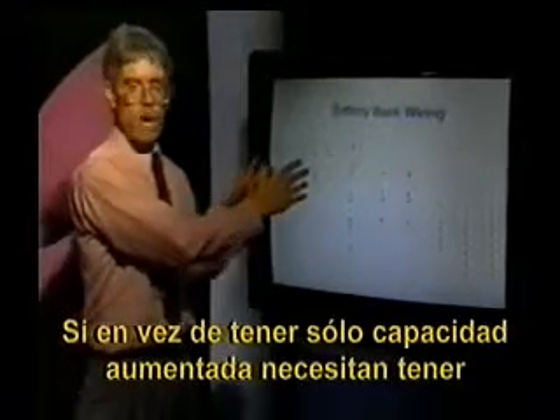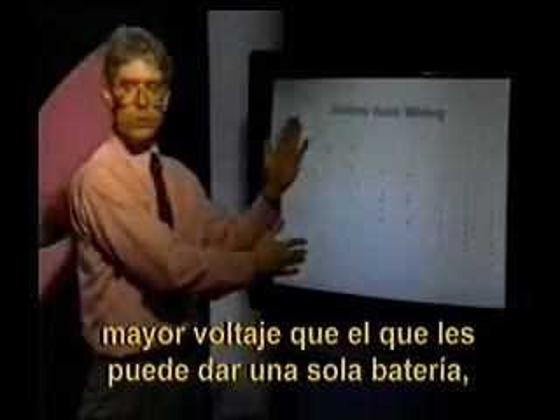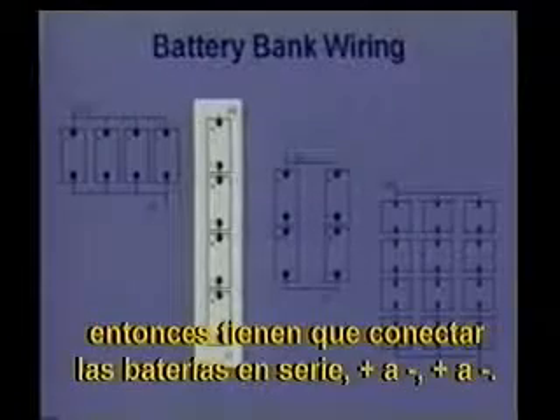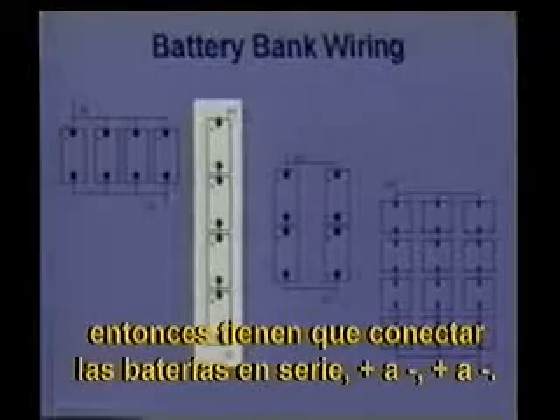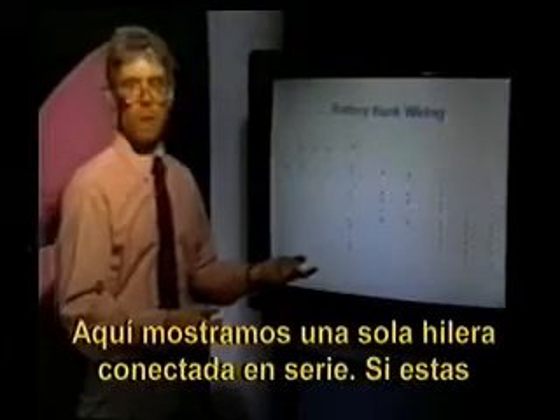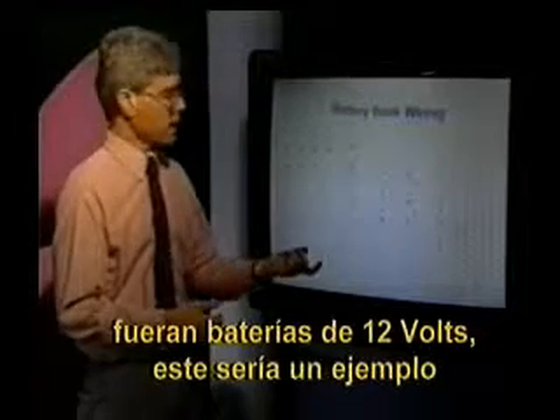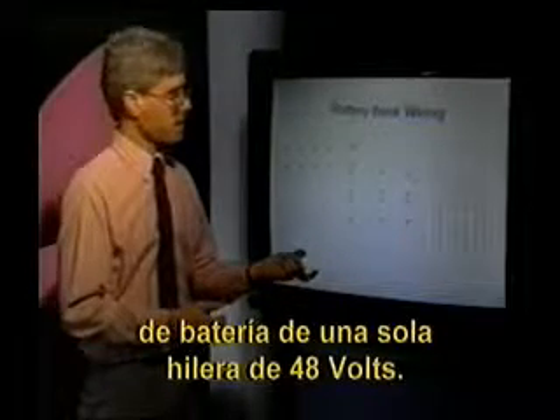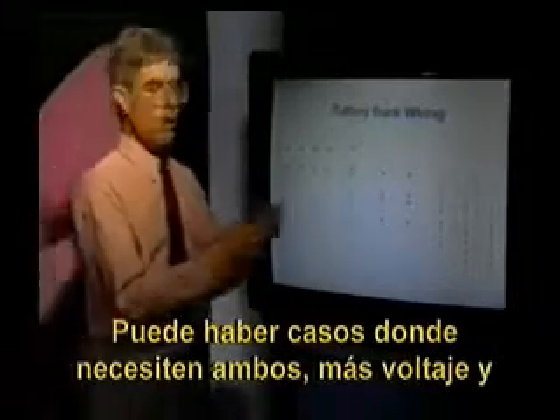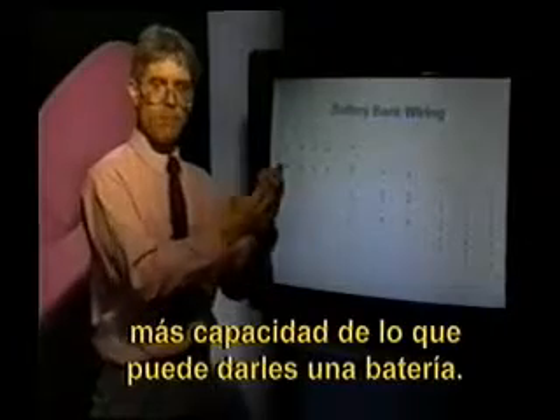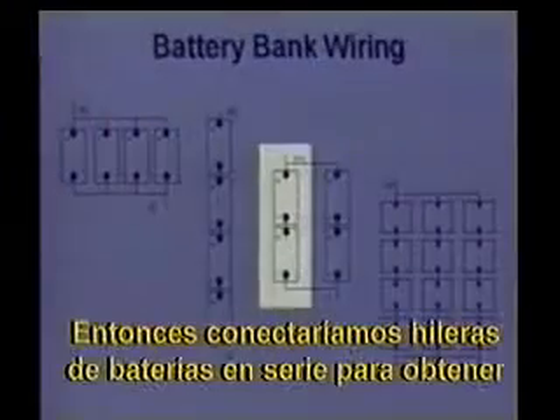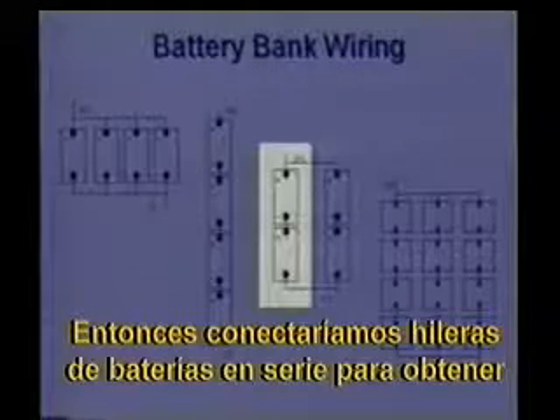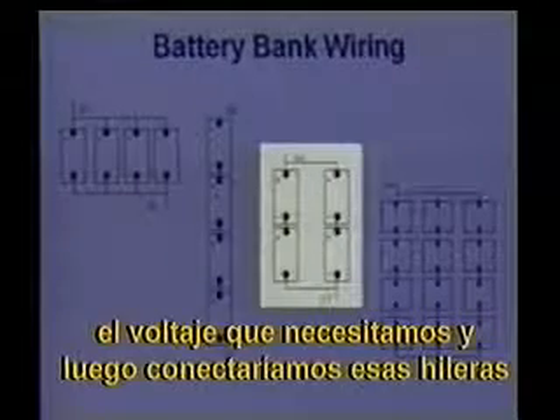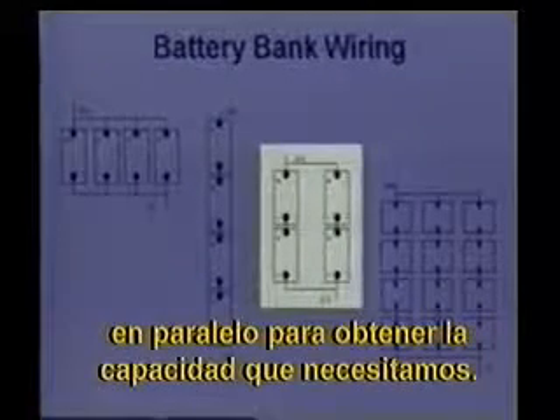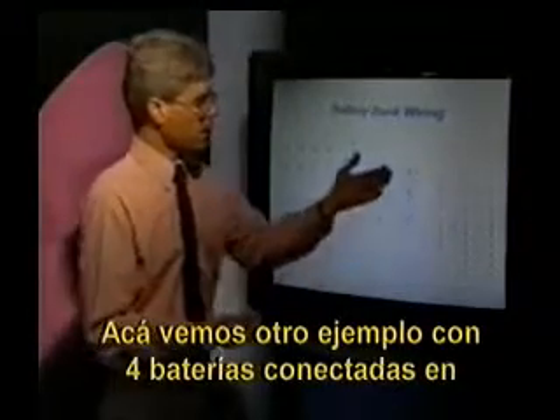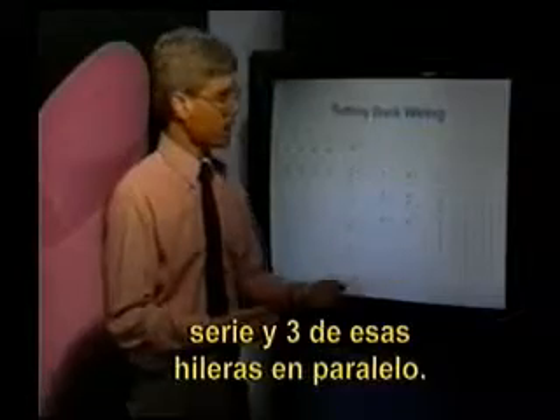If instead of just having an increased capacity, you need to have your battery voltage higher than just a single battery can give you, then you need to connect your batteries in series, plus to minus, plus to minus. Here we show a single string wired in series. If these were 12-volt batteries, this would be an example of a 48-volt single string battery. You may have cases where you need both more voltage than what one battery can give you and more capacity than what one battery can give you. So we would wire up strings of batteries in series to give us the voltage we need, and then connect those strings together in parallel to give us the capacity that we need. A further example is shown with 4 batteries wired in series and 3 of those strings in parallel.